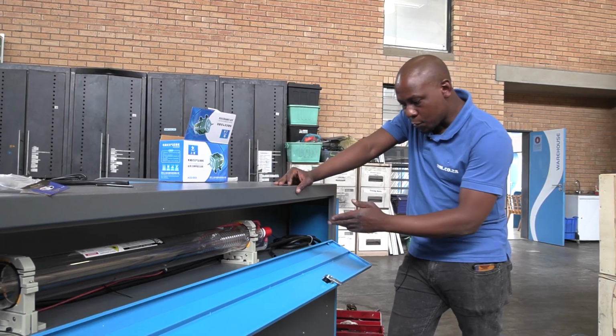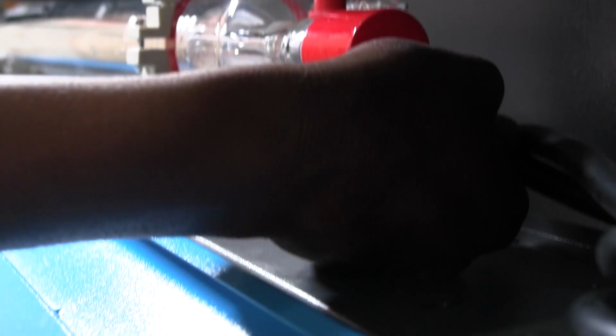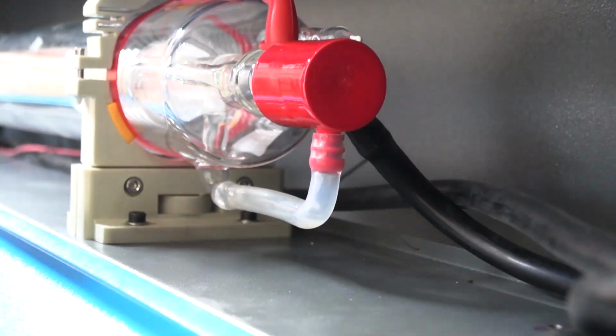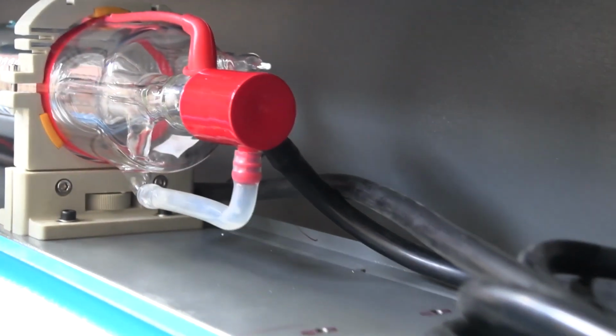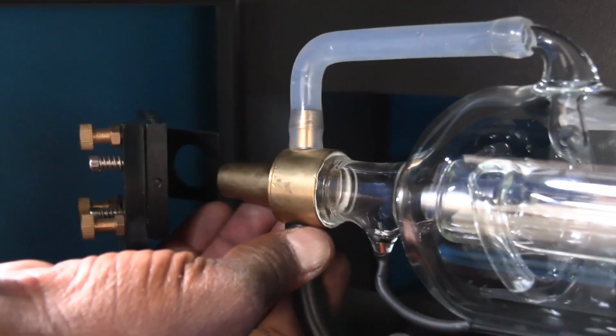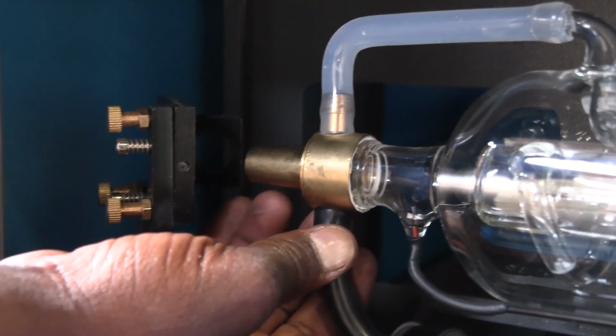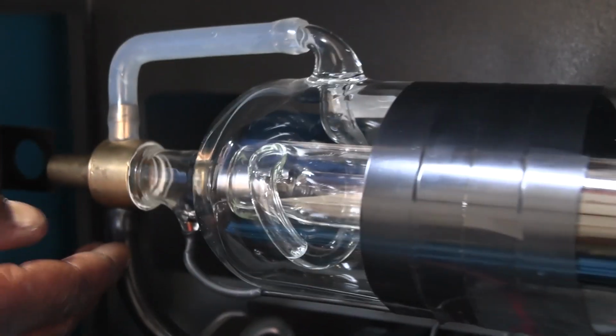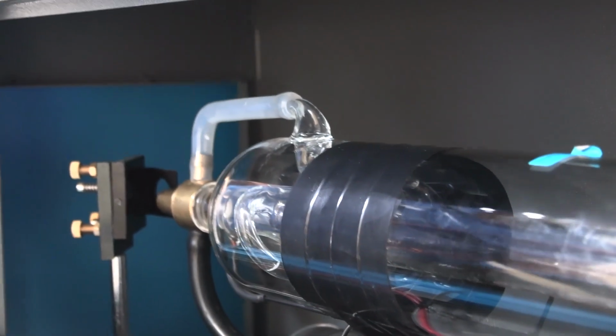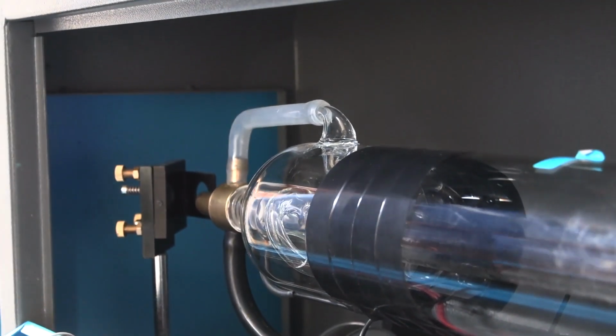The next step is connecting your water into the tube. You just push it in, very easy, and just make sure the pipes aren't folding, otherwise it will block the flow. The same applies with the front of the tube. Just push in the outlet pipe so water gets in from the rear of the tube and comes out from the front of the tube, going back to the chiller, cooled, and returns into the tube.